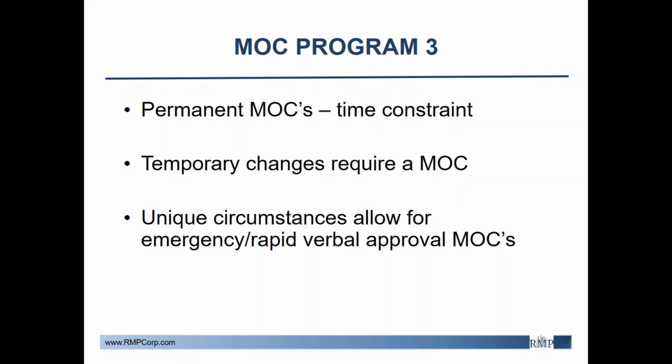If a facility has an emergency rapid verbal approval, MOC procedures should be available. The procedures must clearly outline the specific circumstances that constitute an emergency, identify the approvers who must verbally authorize the change, and how and when the normal MOC documentation is to be prepared during the next business day. Furthermore, these MOC provisions should be used sparingly and never when the normal approvers required by the MOC procedures are on-site or otherwise physically available.